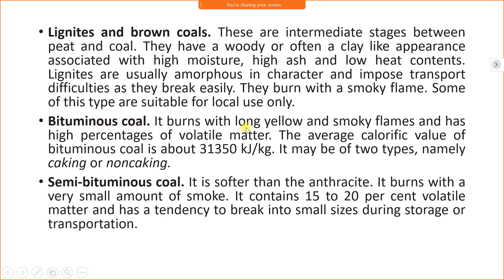Bituminous coal burns with a long yellow and smoky flame and has a high percentage of volatile matter. The average calorific value of bituminous coal is about 31,350 kJ/kg. This is a good fuel and can be used for power generation if anthracite is not available, as its calorific value is above 30,000 kJ/kg. It may be of two types: caking or non-caking.